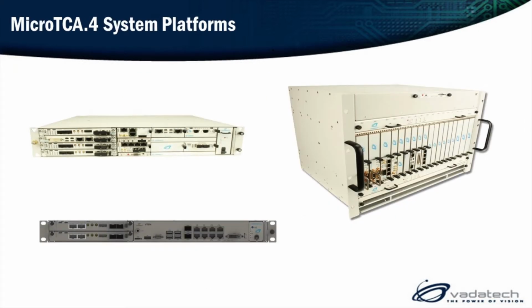So before, for applications like beam monitoring, positioning, and low-level RF, laser, synchronization type of applications, typically this larger type of 8U chassis, 12 slot was a lot more common. Now we're talking about going to requirements where you have, for example, just a 6 slot in a 2U, really saving a lot of space.